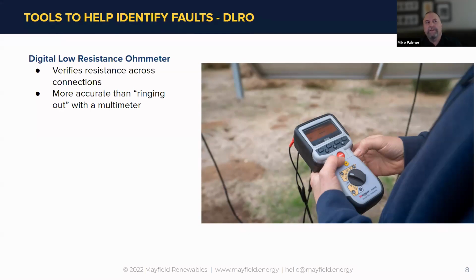Those change in measurements of the DLRO, and a DLRO measurement, just to get into it briefly, is a 4-wire Kelvin test. So we're going on both sides of that connection, and we're flowing current. And the handheld that's in the picture here is a 2 amp DLRO. This came to existence really in the wind segment with testing the electrical connection at the turbine blades all the way to earth. And so we have a cable reel with over 300 feet of DLRO cable on it to do this test while our rope partners are hanging 300 feet out of the ground. You used to have to do this test in another way with a big box. Now we got a handheld, and we're going to start talking about using that DLRO2 to test these connections.